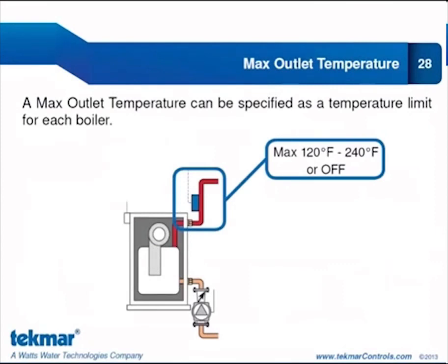Each application showed all boilers with individual boiler outlet sensors. New to the 284, we can use those outlet sensors not just to monitor outlet temperature but also as a limiting device by selecting a maximum outlet temperature for each boiler. The range is 120 to 240°F. If you only want to monitor and not limit, you can turn the max setting off. This gives us the opportunity to limit individual boiler temperatures — a fantastic new feature that sets the 284 apart.